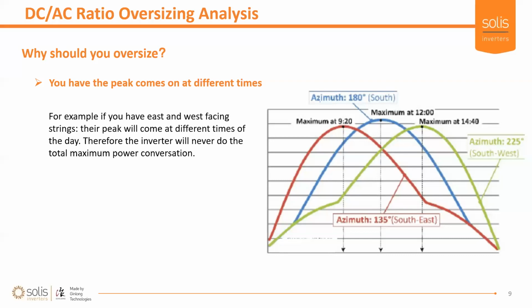For example, if you have a 5 kilowatt inverter, you have 3 kilowatt peak of solar panels facing east and the other 3 kilowatt peak facing west. In the morning when the sun is rising, the sun is shining more directly on the east facing string. That string could be generating the full 3 kilowatts, whereas the west facing string will not be at the peak and the inverter will not need to convert the full 6 kilowatts. It will obviously be less. And then conversely, in the late afternoon, you will see that the west string will be peaking, whereas the east will be dropping away, as you can see in the graph.